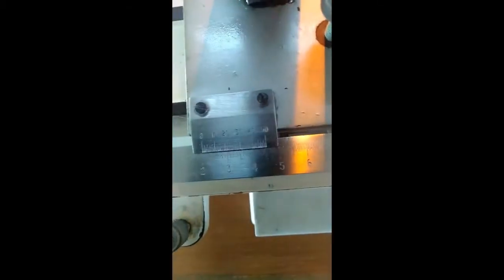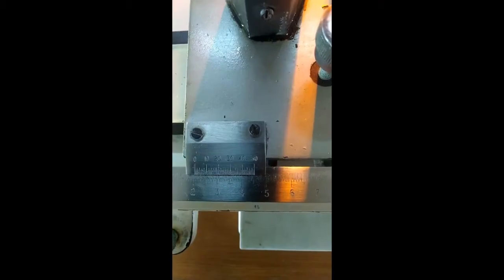This is the main screw used to change the horizontal distance of the traveling microscope. See, if we loosen the screw, this traveling microscope can be slid easily on this main scale. Right? If this main screw is tightened, we can use the tangential screw to make fine adjustments. We need to keep this main screw in a tight position. Then we can use the tangential screw.